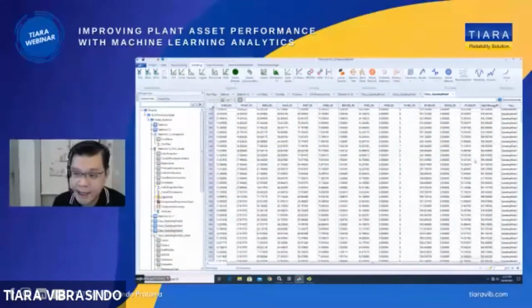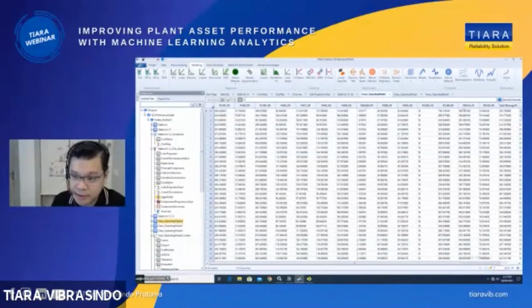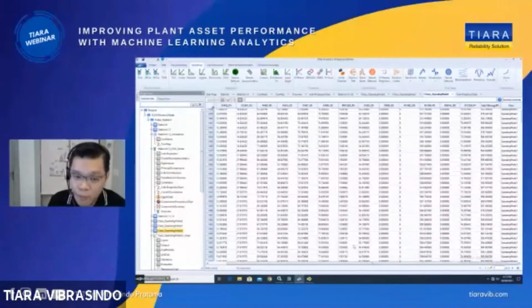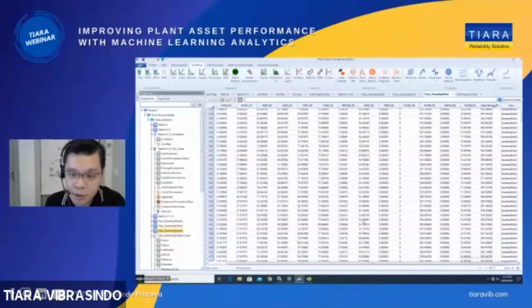And if you want to model energy consumption in operating mode 3, if you have 1 table that has everything inside, your model will not be accurate, because as you can see here, if I split into different operating modes, you realize that different operating modes have different energy consumption. This one has higher energy consumption compared to this one, lower energy consumption. So if I want to model, I need to split. If you remember, I need to use PCA to recognize different operating modes, and then split them up into different data sets. Once I arrive at this data set, then I can accurately create a model.